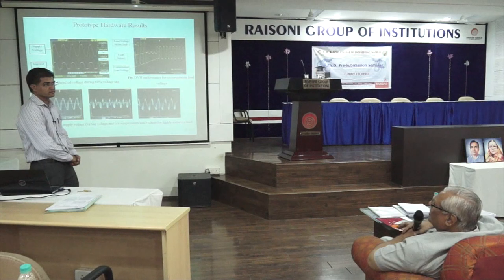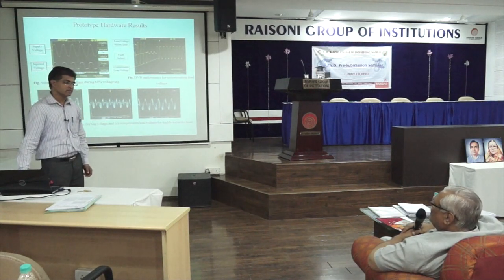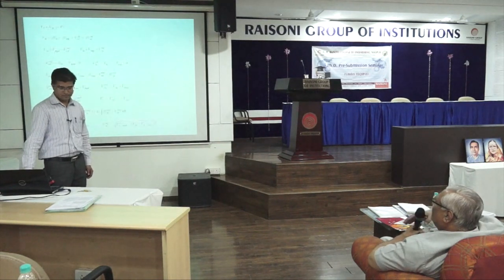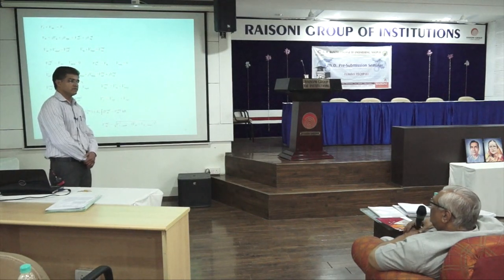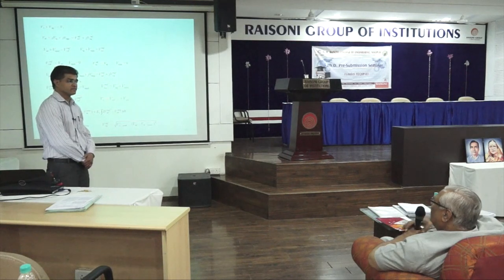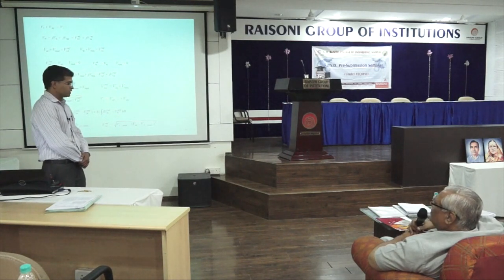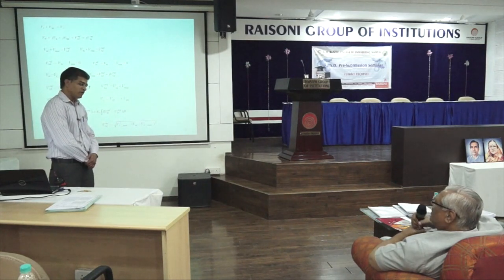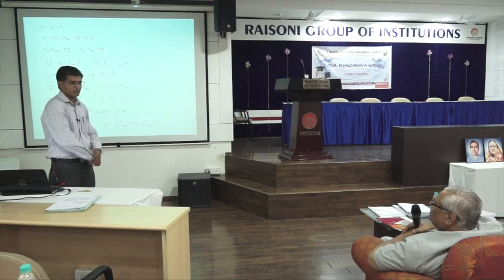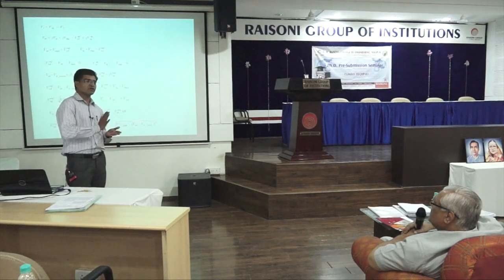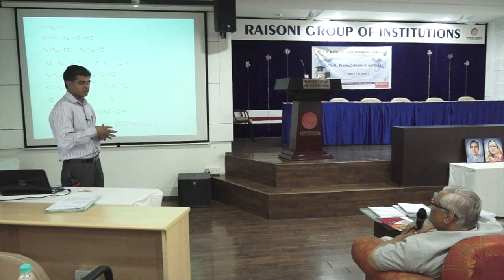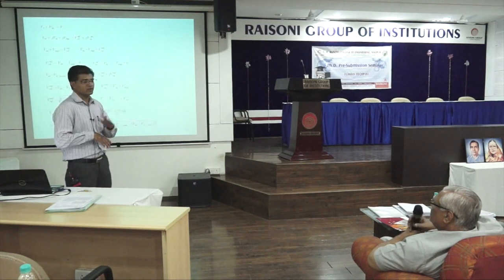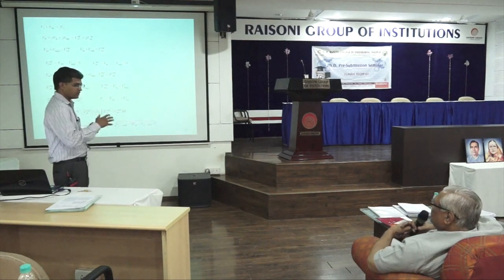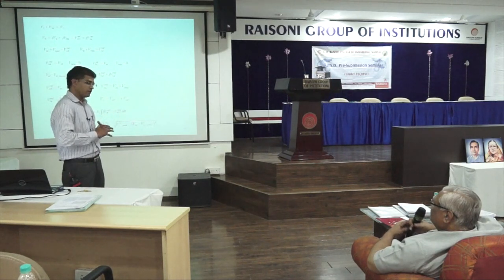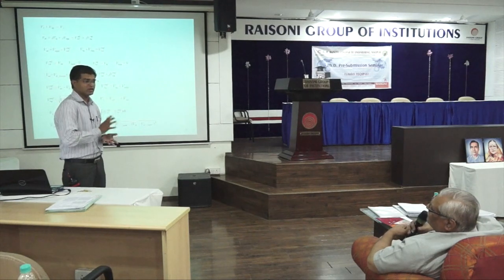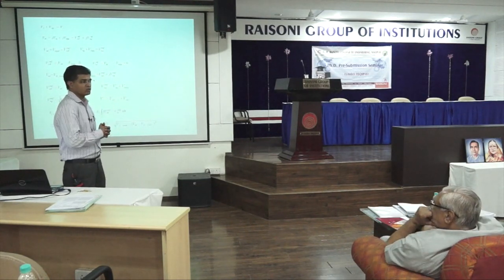These are all commercially available DVRs. The device is available, and power quality problems in industrial areas are also there, and people have used DVR itself. What do you feel is your contribution? These controllers and filters already exist. Many of the controllers are based on instantaneous values, and most are based on symmetrical components. I have used the SRF theory, which works on average value. So it gives exact detection on the voltage side, so that the voltage injection and power injection are minimized, and the size of the energy storage device can be minimized, so that it can be cost effective.